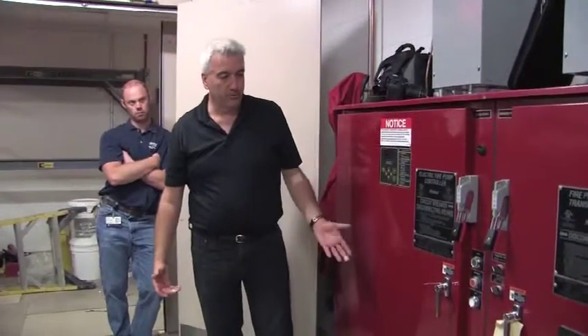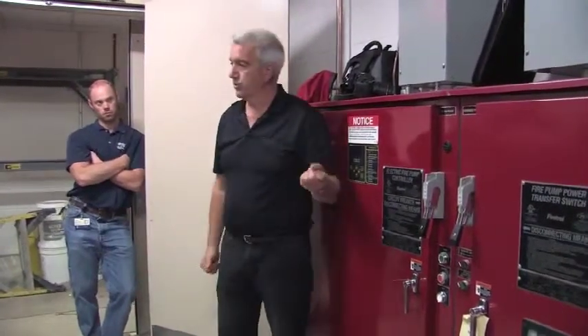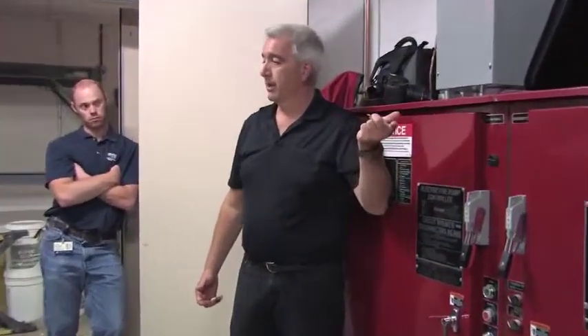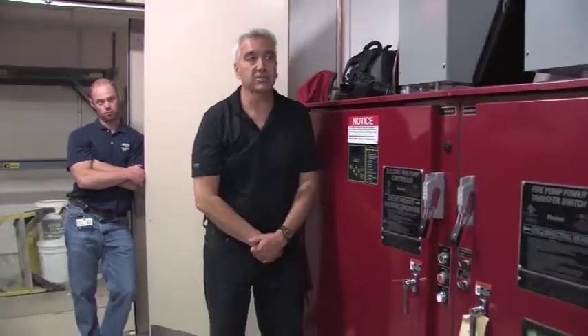What we always recommend for a weekly test is to open up a 2-inch drain that's system-wide, if your system can handle it. In fact, a couple of the guys and I were talking earlier about how to do that. You don't always have to shut off the discharge valve, but in some buildings you like to have it off so you don't bump the dry systems. Yeah. So it's all a judgment call with you guys as to how you typically would test a system.